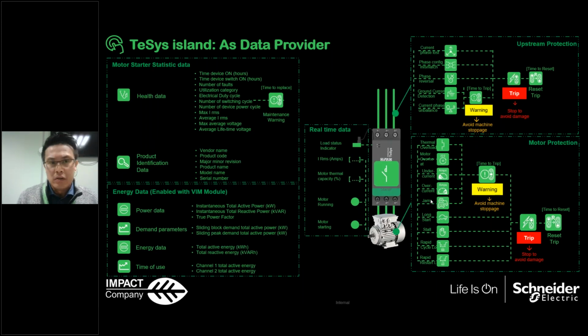So this is all the data we can have from the TeSys island. The TeSys island is a data provider, so not just the current. You will see that we can also have health data: the time the device is on, the switch-on count, number of faults, and then utilization category, duty cycle, switching cycle, maximum current, average current. This is all the health data we can have in the TeSys island without any additional modules. Everything is already ready in the bus coupler, and you just set the bus coupler through the Ethernet, and then you can have all this data. We can also have the product identification data: the vendor name, the product code, the product name that you can set in the system. For the energy data, you can have the power data, demand parameters, energy data, time of use. This is all ready for you to have.